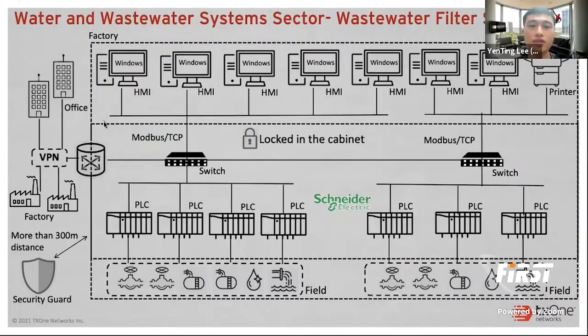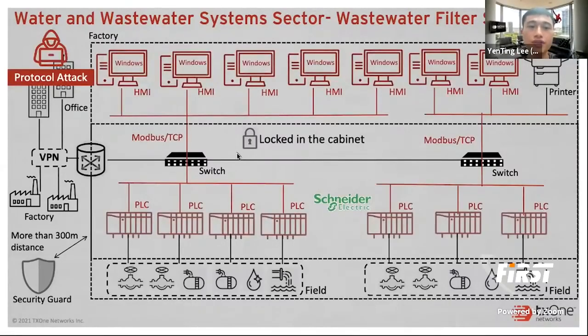In our exercise experience, we even found that they had a switch using the default password. This condition could allow an attacker to paralyze the system. As aforementioned, attackers have many ways to enter a factory network. In this case, because the system uses the Modbus protocol, it's easy for an attacker to sniff and analyze the traffic. After that, the attacker can perform command injection to the HMI or PLC. It may result in the HMI getting wrong information or the PLC executing unsafe commands.